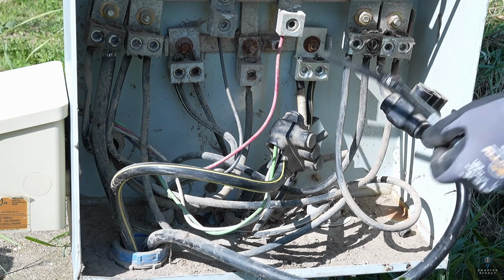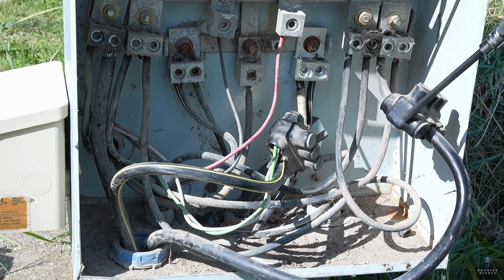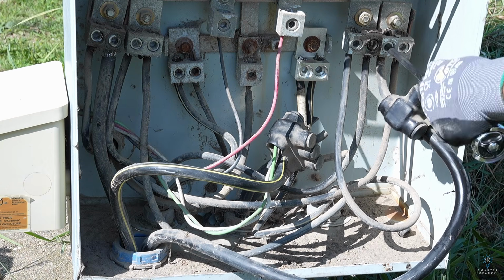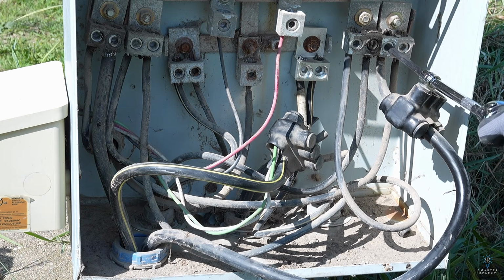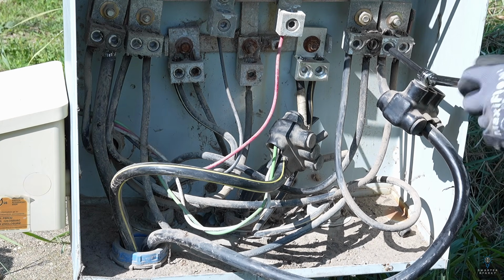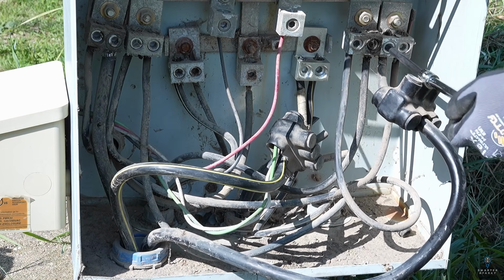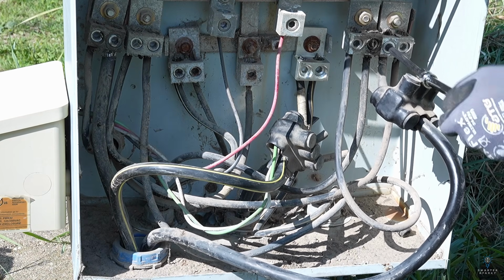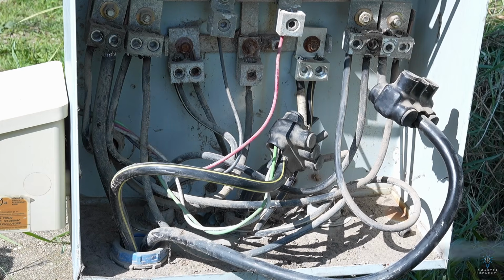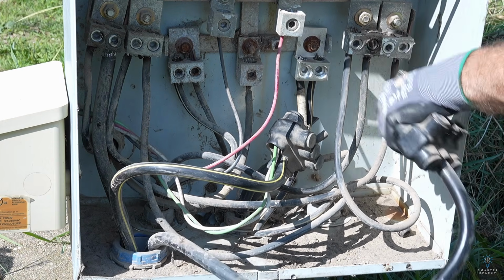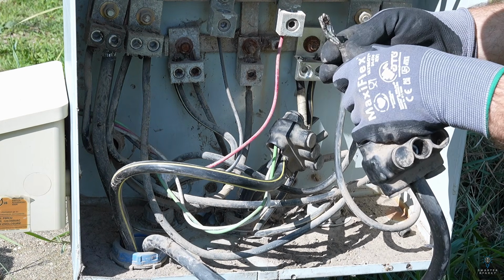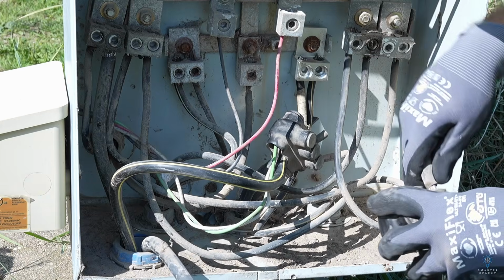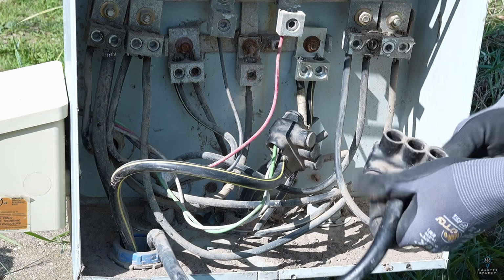There we go. Might as well fix this hot while everything is de-energized. I'm just gonna loosen it up completely, reseat everything. Make sure the conductors aren't damaged. No, they're not damaged. Just dirty. Oh geez, that's loose in there too.